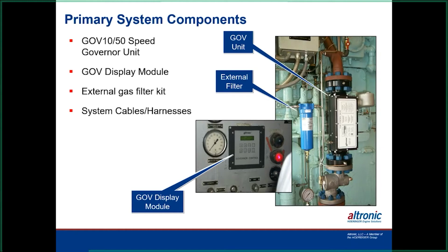GOV10, the governor on it, the display is, you don't need the display with all the newer PLCs and stuff that are out there now. We can communicate directly to the valve. So if you want to build some type of graphics or something along that line in your newer PLC, or maybe a DE4000, we can tie directly to the valve to do that.